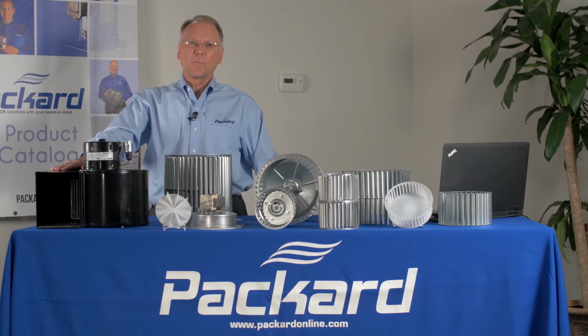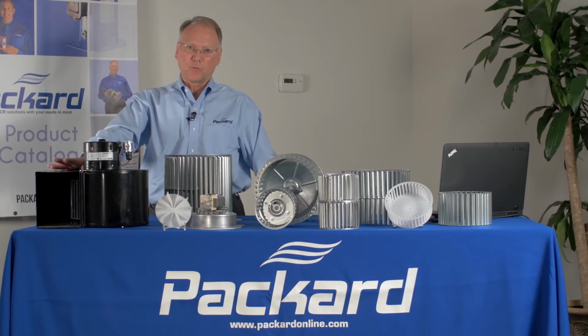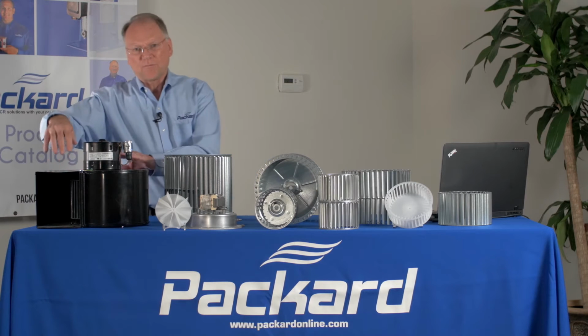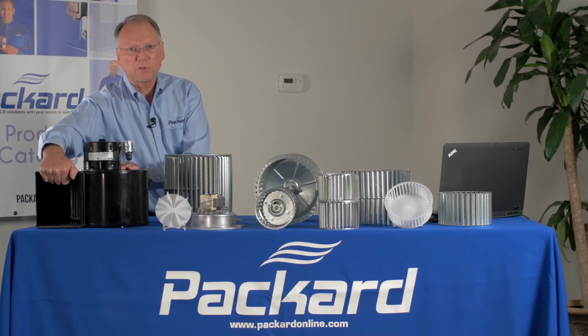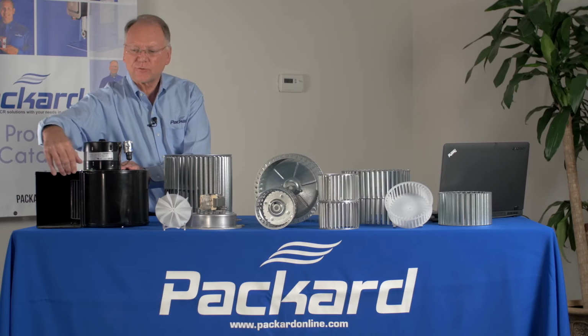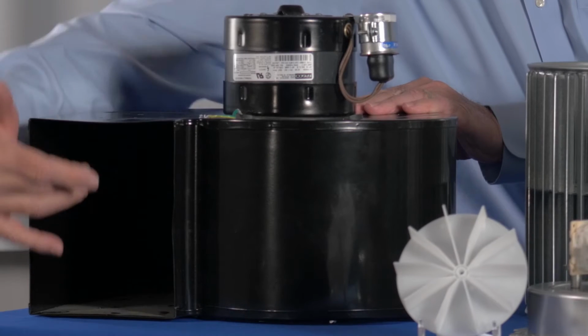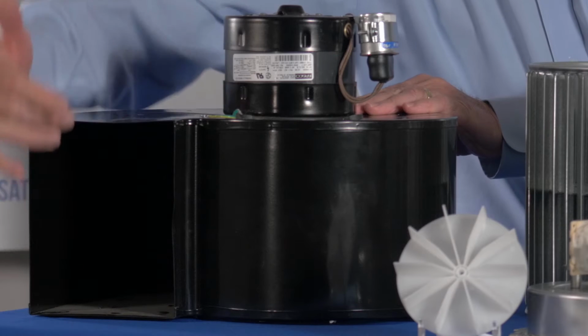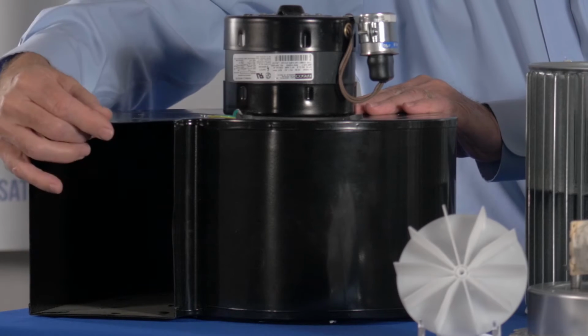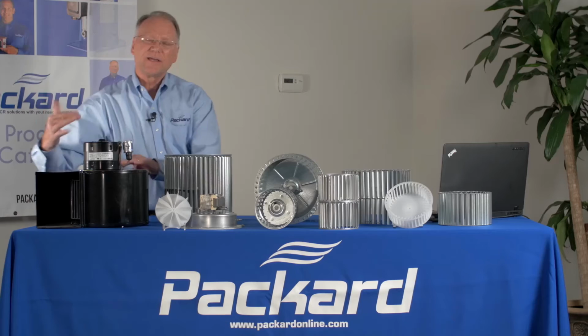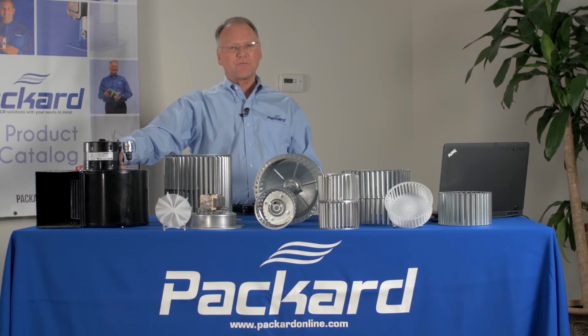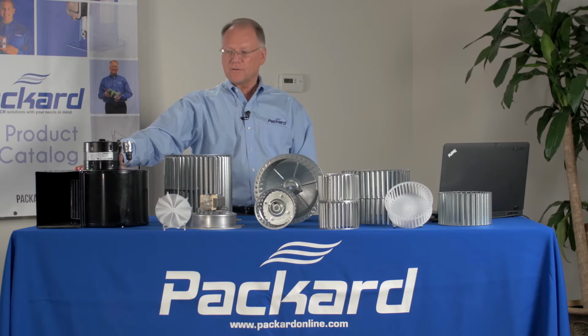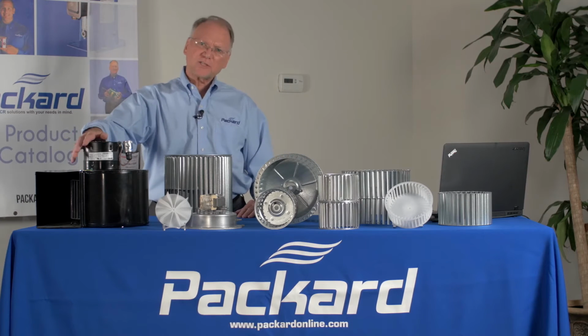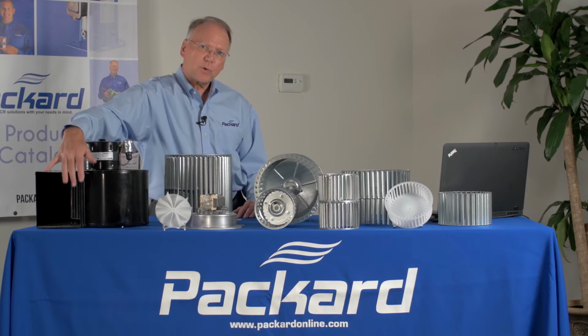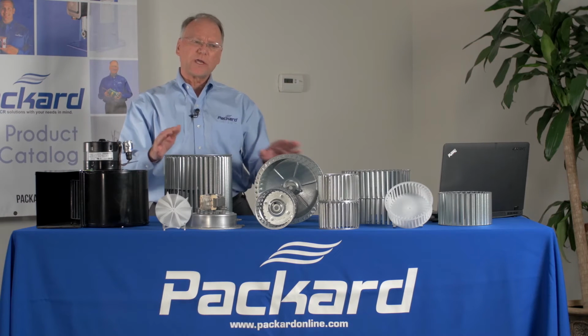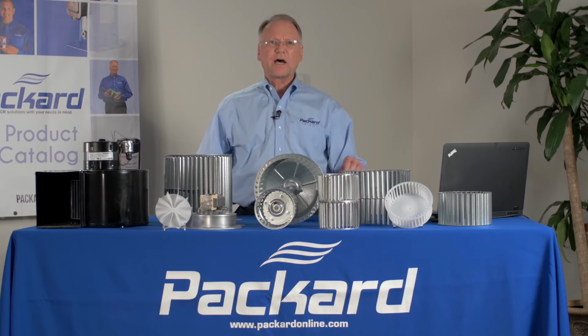Blowers are critical components in heating and air conditioning equipment. Before removing a blower wheel from the blower housing, be certain that you identify the location of the wheel within the housing so that when you reassemble the replacement wheel in the housing, it's in the proper position, giving you proper performance.